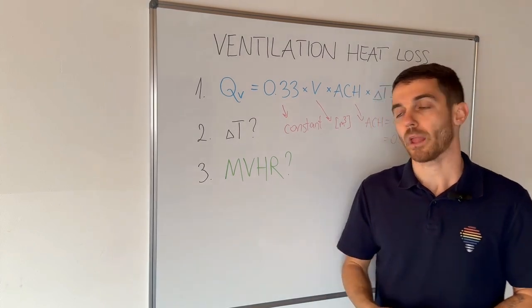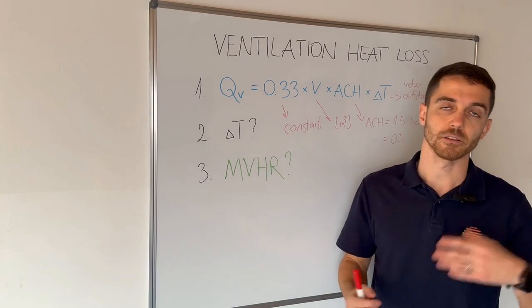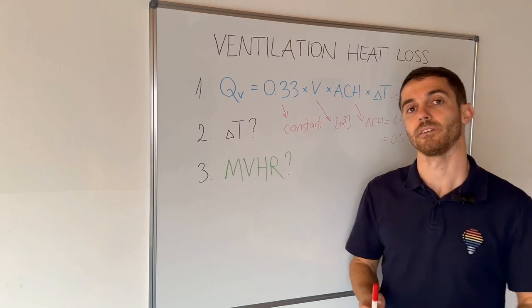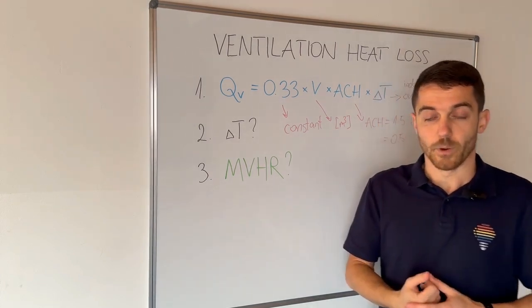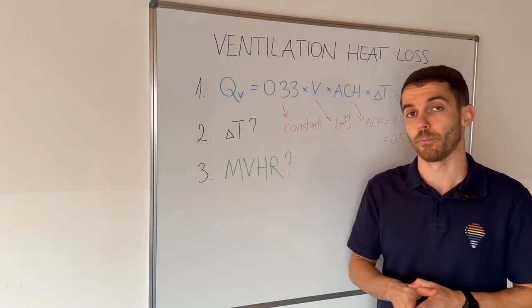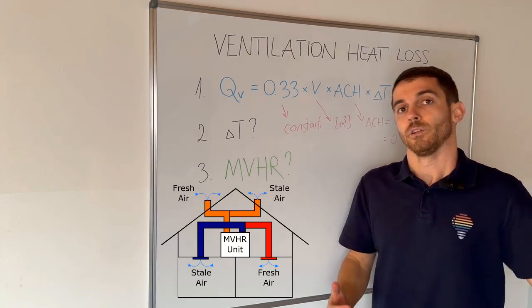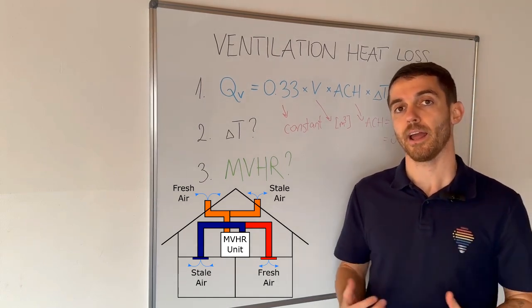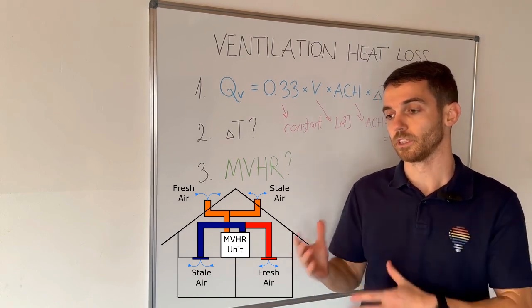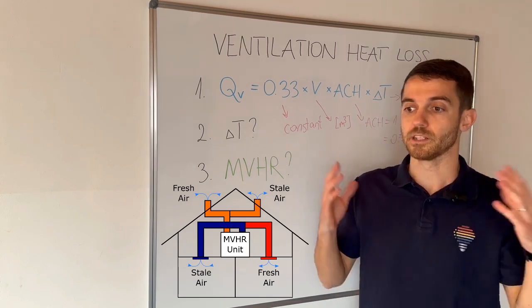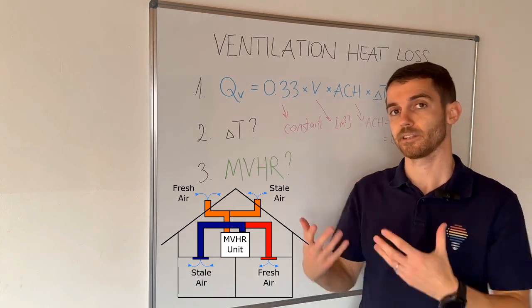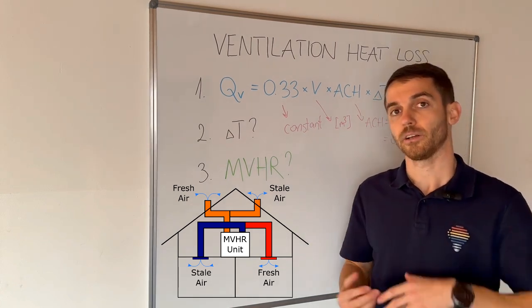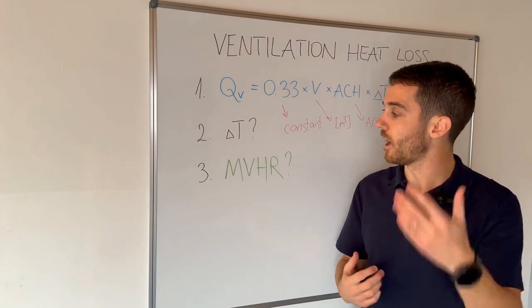The last point is that in Croatia, and I assume in other countries as well, not a lot of new builds or reconstructions are installing MVHR — mechanical ventilation heat recovery. This means installing a device in the house with four pipes: supply clean air from outside into the indoor rooms, and stale dirty air from inside going outside. Inside the unit is a heat exchanger, so we are not losing the hot air as we would if we opened a window. We recover heat and lower our ventilation heat losses.